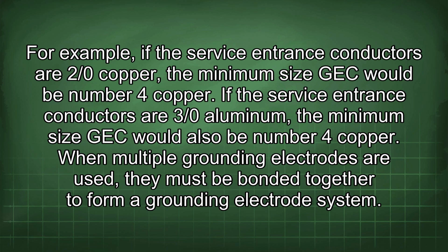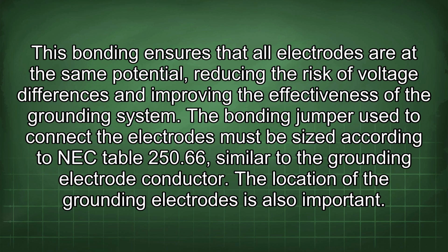When multiple grounding electrodes are used, they must be bonded together to form a grounding electrode system. This bonding ensures that all electrodes are at the same potential, reducing the risk of voltage differences and improving the effectiveness of the grounding system. The bonding jumper used to connect the electrodes must be sized according to NEC Table 250.66, similar to the grounding electrode conductor.